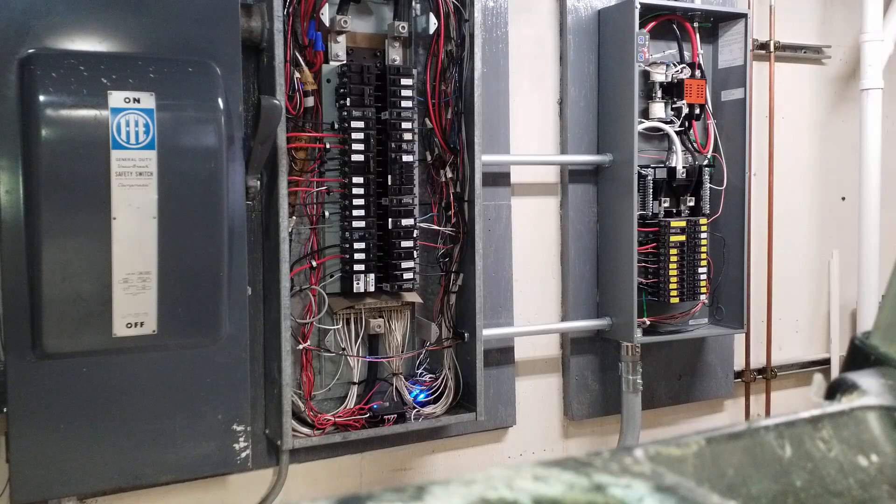Wow, it's been six and a half minutes. And there we are — we are back on full utility power. The red light on the generator panel indicates that the generator is going to continue to run for several more minutes. But that's all functional. It took over five minutes to switch back once the utility power was restored, but it does work!